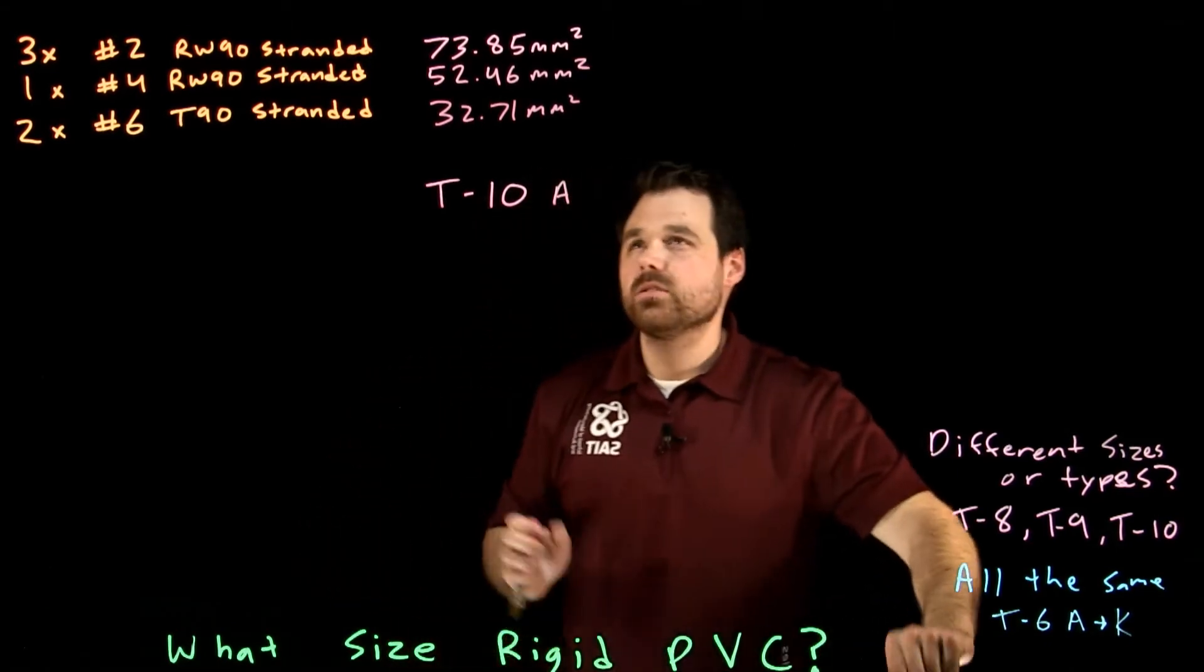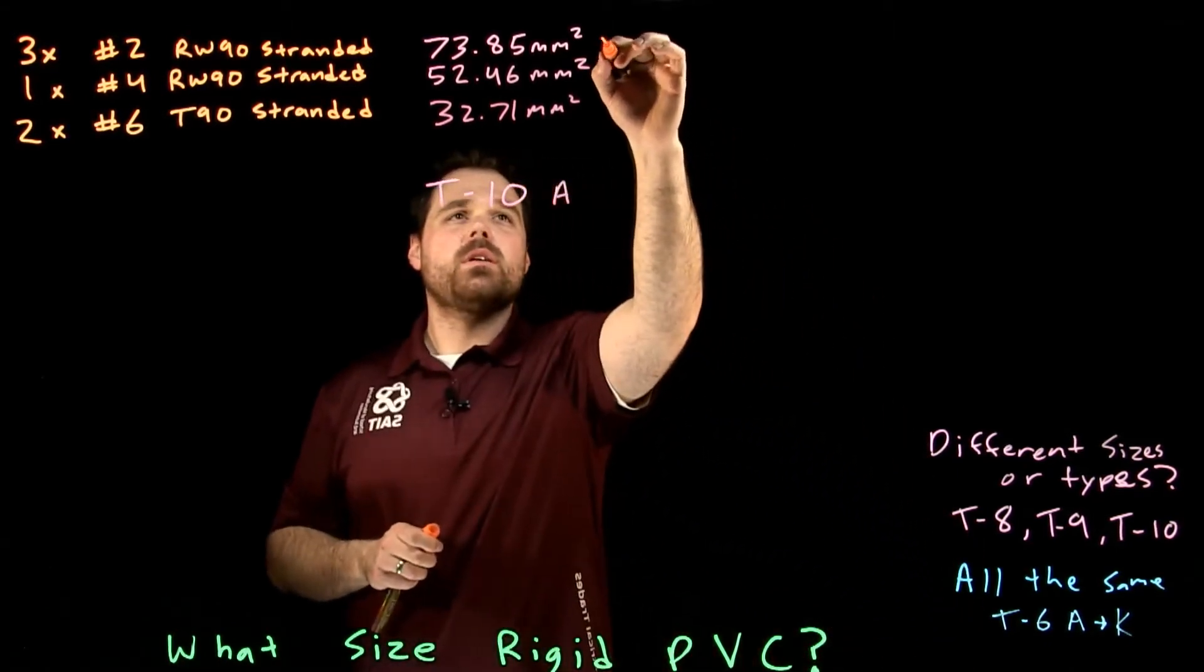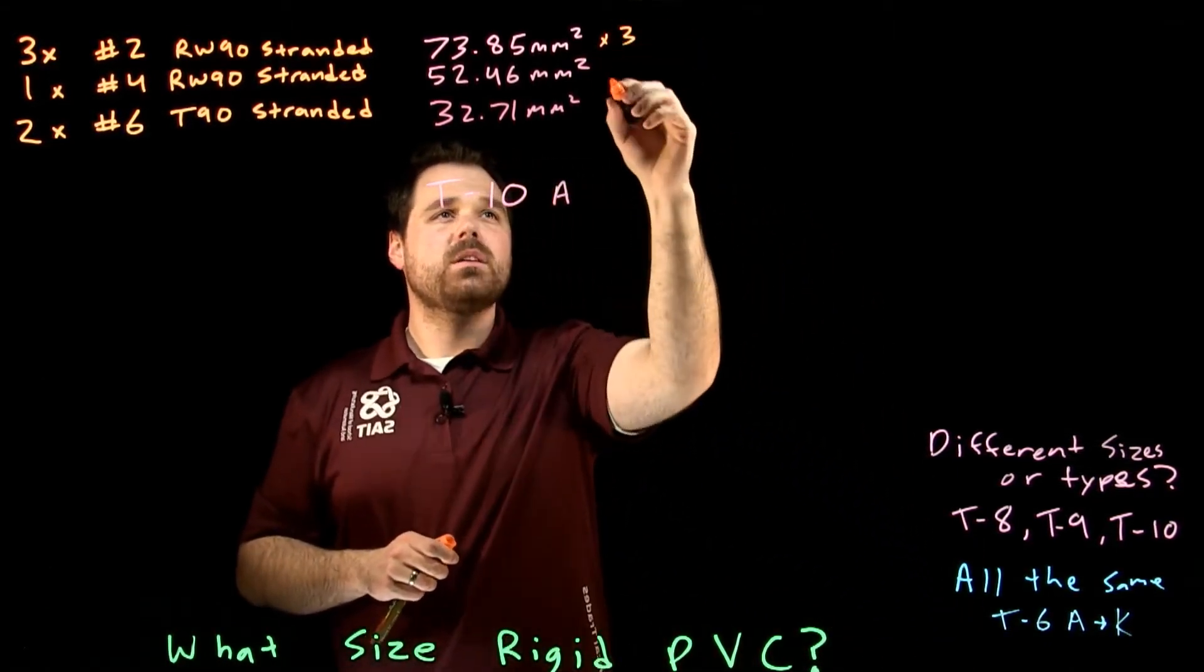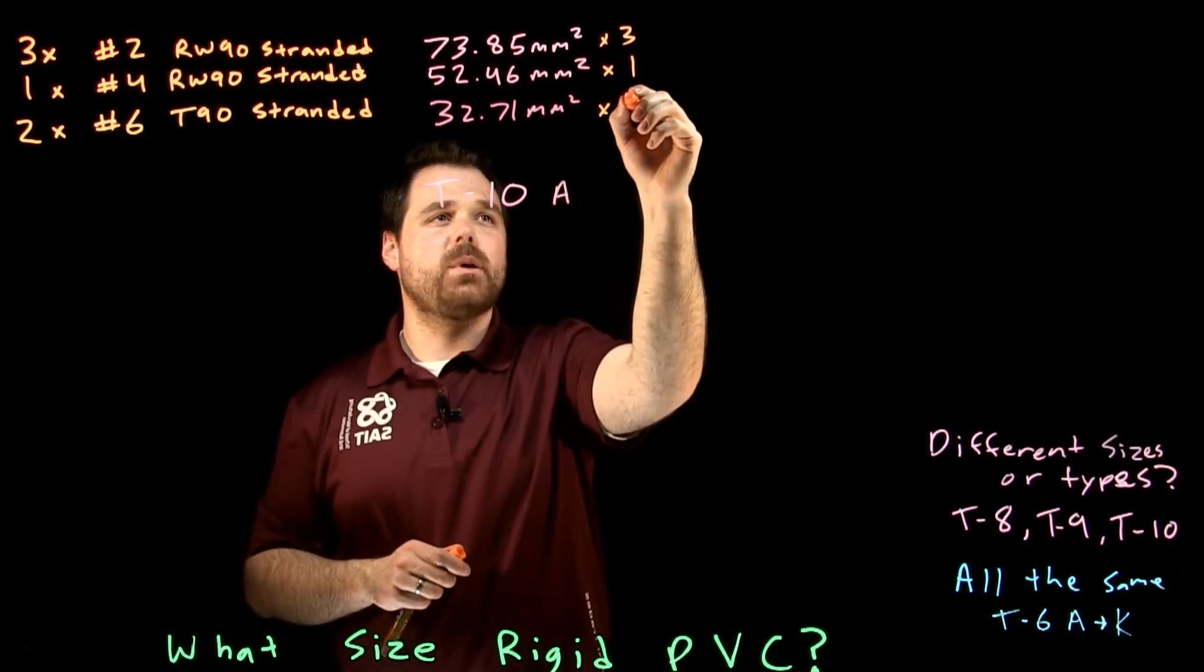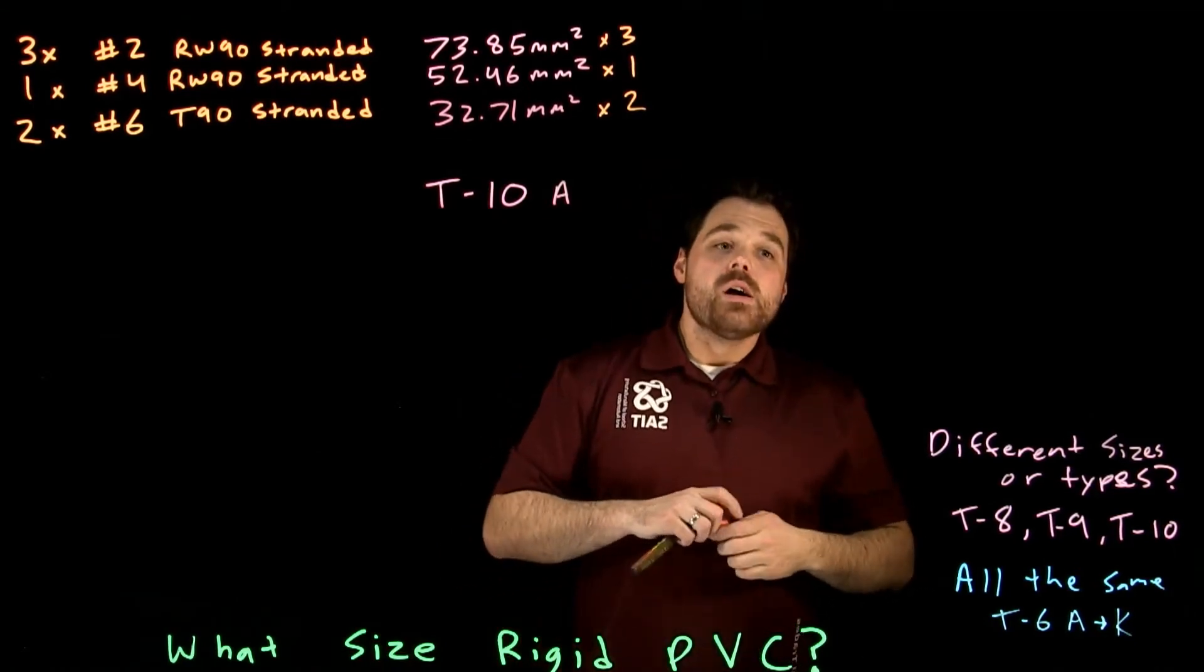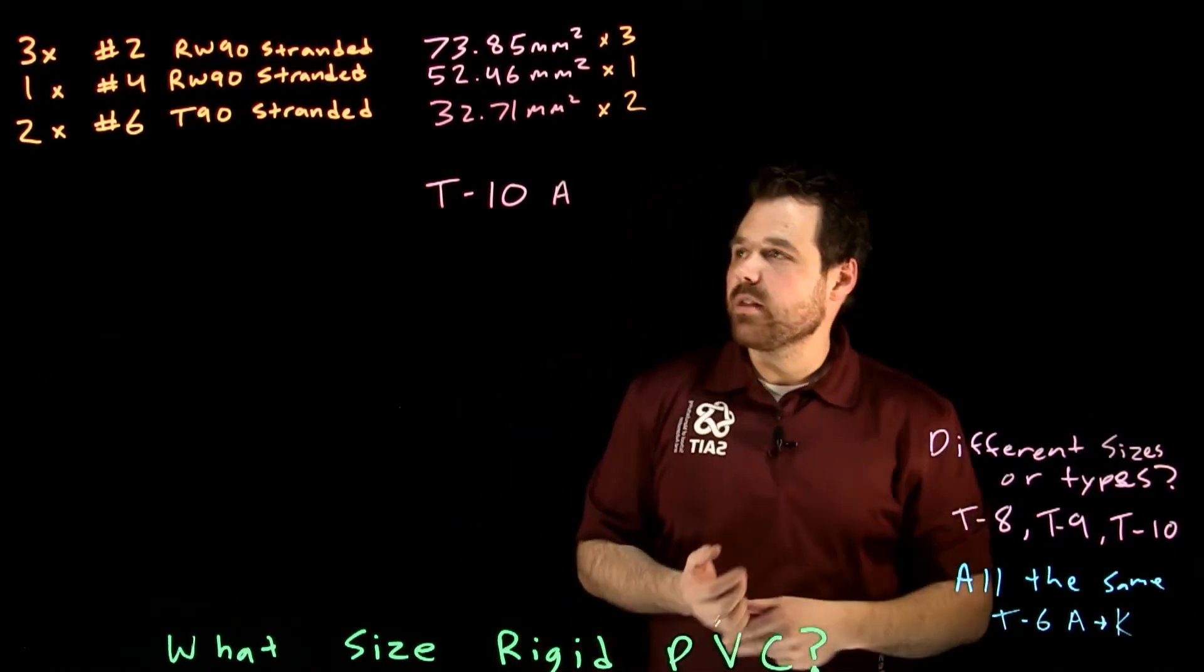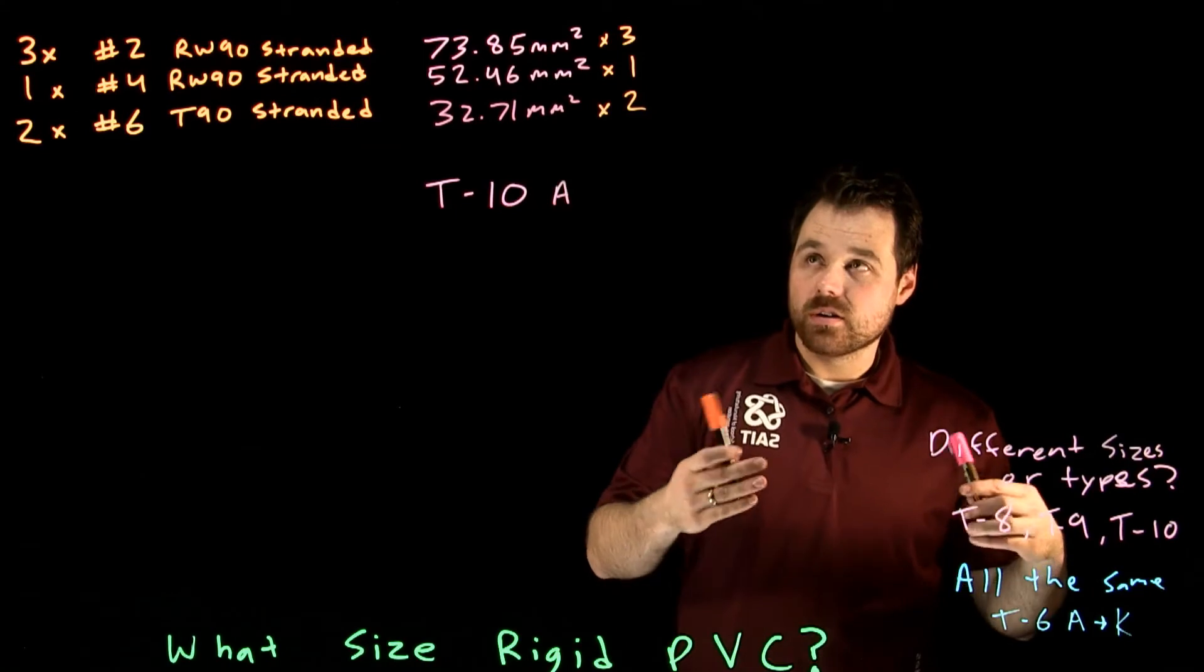Perfect. Then I take that and I go, okay, I know I have, multiply that by three, multiply that by one, because that's how many I have. Multiply this guy by two, because that's how many I have. That's going to give me the total area that all of those conductors are taking up.